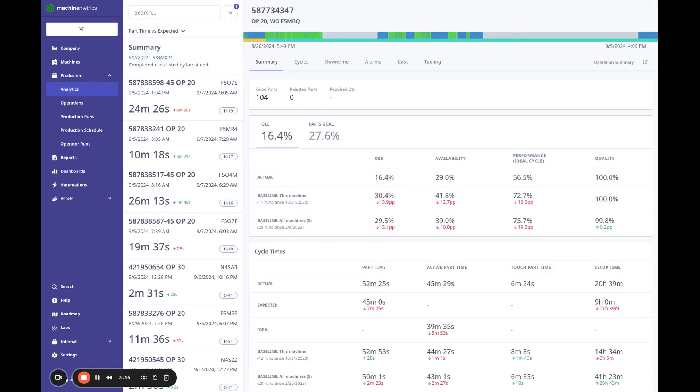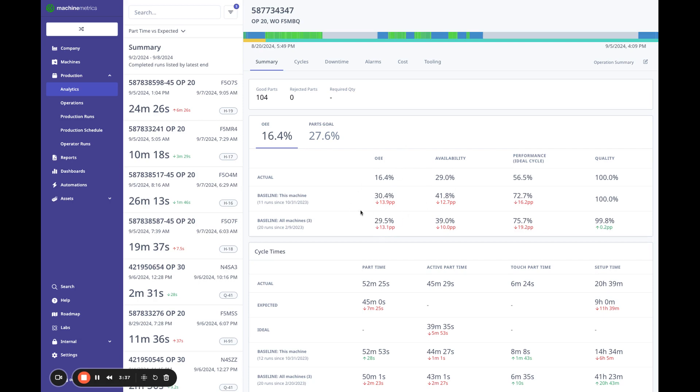We can see we ran 104 parts. Our OEE is 16% where typically we run at 30%. You can see here, we've baselined this machine, but we've also baseline on all machines, just ran on three different machines. So if you want to look at the difference, perhaps the machine that you're running on is performing different than the other machines. And I can see that I have an issue both in availability and performance here. That's what's driving my OEE down.